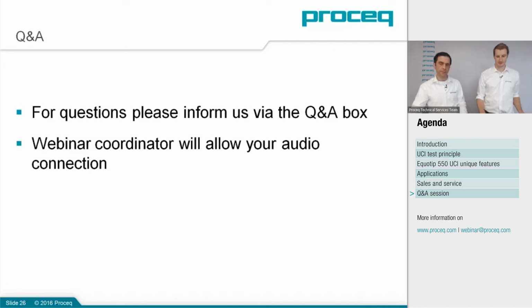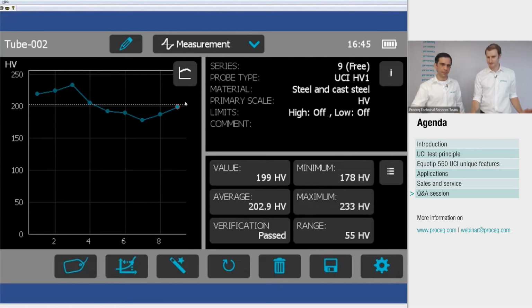Could you show us how easy it is to change the test load on the Equotip 550 for the UCI probe? Yes, sure, I'll switch to the instrument again. You see here in the upper right corner the probe type, and here it says UCI HV1 - so at the moment we are using the probe with HV1 test load. Within this measurement series, we cannot change it; within one measurement series, you can have only one test load.